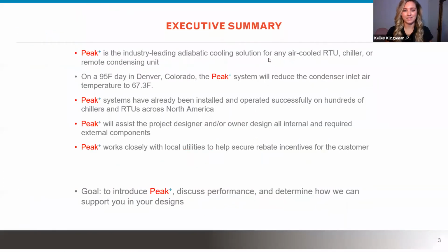All right, Peak Plus, just to give you a quick summary of what we're going to talk about. Peak Plus is the industry-leading adiabatic cooling solution for any air-cooled RTU, chiller, or remote condensing unit. We work with units from as small as 5 tons all the way up to the max tonnage that can be built. Further on, in the performance in your territory in Denver, Colorado, on a 95-degree day, the Peak Plus system will reduce the condenser inlet air temperature to 67.3. And I'll show you how we're going to do that in a couple of the other slides.